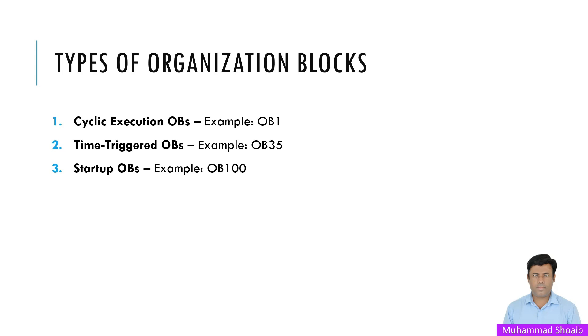Then we have the startup OBs, for example OB100. When your PLC powers up or restarts, OB100 runs first. It's perfect for initialization tasks like resetting the counters or putting some static value inside the variable for the default value.